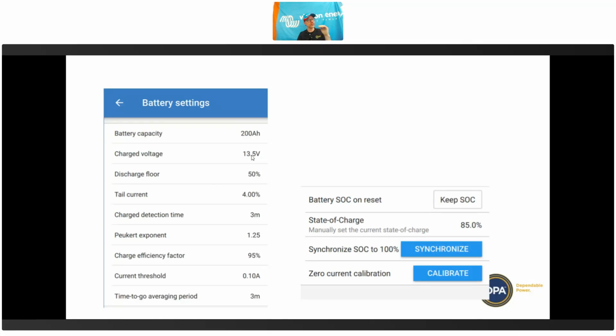But it's not just when it sees that voltage, it's when it is at that voltage and then we go down to this setting we've got here, charged detection time. So when it's at 13.5 for 3 minutes and the current is 4% of 200 amp hours, that's the tail current we've got here. So that would be 8 amps, right? That lets it know that it's at the end of the absorption cycle, because it's reached this certain voltage and the current has been low for an extended period of time, and that lets it understand that you've probably finished absorption and are in float. That's what it's trying to detect.